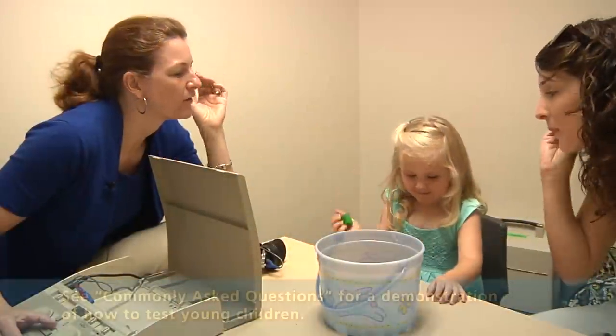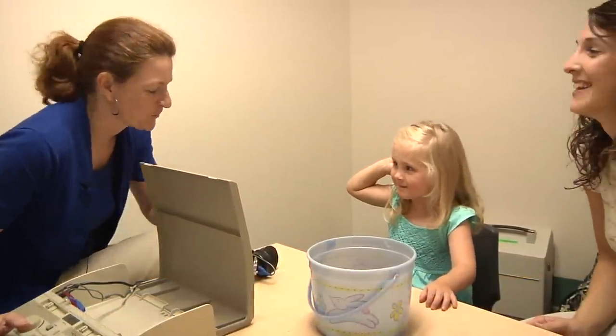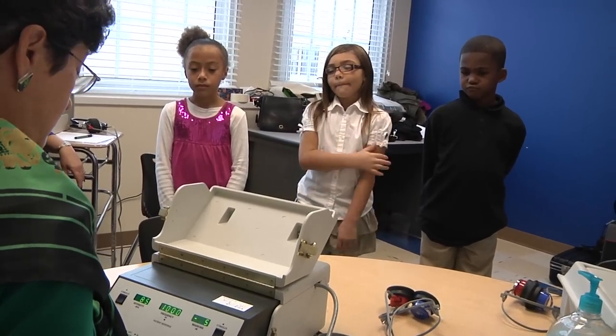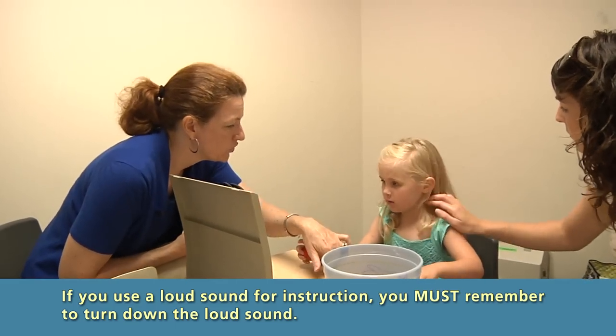Use the following instructions to prepare students for the hearing screening: 'I am going to put these earphones on your ears. You are going to hear some beeps in your right ear, and then in your left ear. Raise your hand every time you hear a beep, even if it is very, very soft. Put your hand down when the beep goes away.' Give the student frequent praise for listening carefully. If a student does not seem to understand the directions, remove the headset and repeat the instructions. For young children, practice the hand raise before the earphones are placed. If you do a demonstration by presenting a loud tone such as 100 dB, you must always turn the intensity down before placing the earphones on the child, as a 100 dB tone can be painfully loud next to the child's ear.